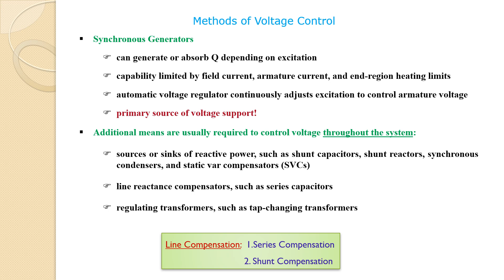The shunt capacitors and reactors and the series capacitors provide passive compensation. They are either permanently connected into the system or in switched form, where they can be switched in steps when required. Shunt capacitors and reactors contribute to the voltage control, and the series capacitor helps in improving the transmission efficiency and stability of the system. Synchronous condensers and static var compensators (SVCs) provide active compensation. The reactive power absorbed or supplied by them is automatically adjusted so as to maintain the voltages of the buses to which they are connected.